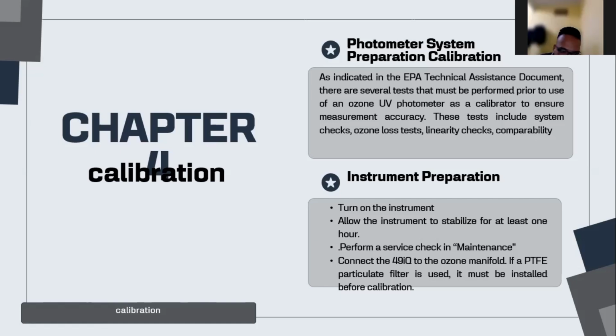Connect the 49iQ to the ozone manifold. If a PTFE particulate filter is used, it must be installed before calibration.